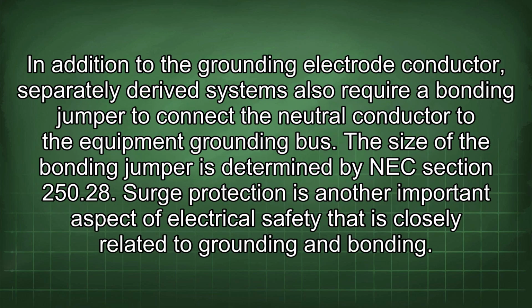In addition to the grounding electrode conductor, separately derived systems also require a bonding jumper to connect the neutral conductor to the equipment grounding bus. The size of the bonding jumper is determined by NEC Section 250.28. Surge protection is another important aspect of electrical safety that is closely related to grounding and bonding.